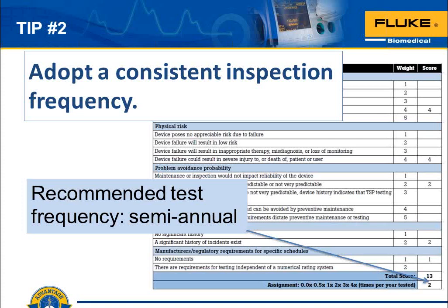So if the score is 13 or higher, the idea is that you would inspect that medical device twice per year, usually every 6 months. If the score is 9 to 12, then you'll test that medical device once per year. If the score is 8 or less, you have a choice. You can do biannual, that means every 2 years testing, or you can test during the incoming inspection and post-repair, but not assign any other interval.